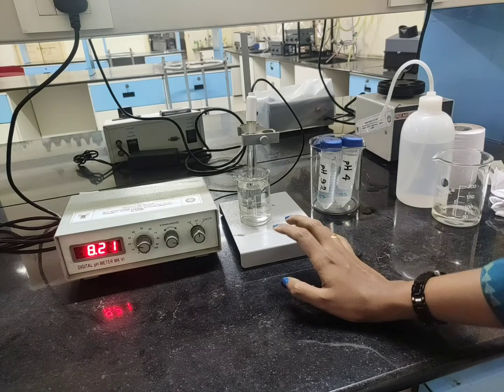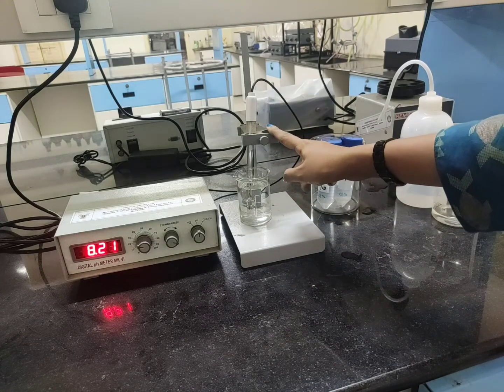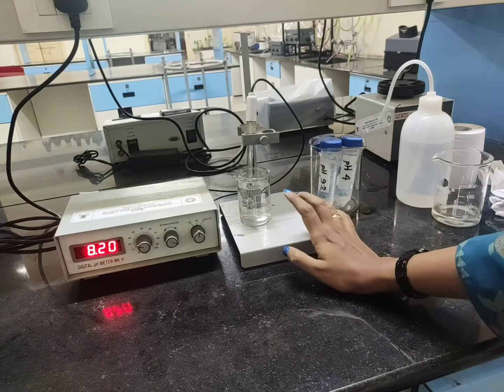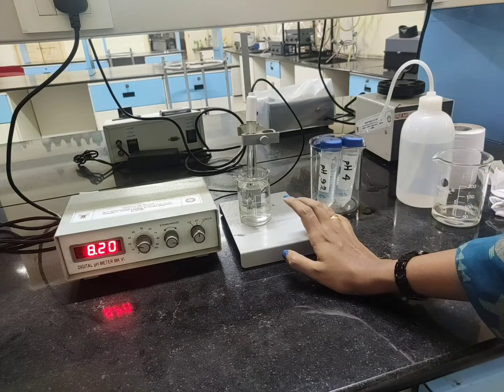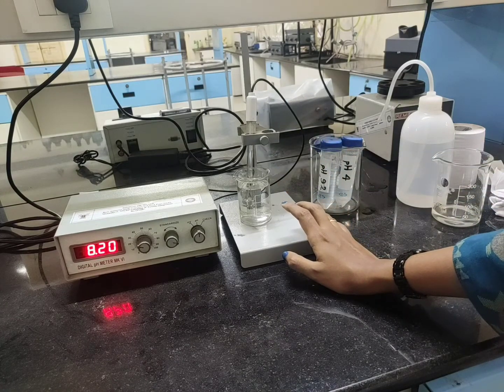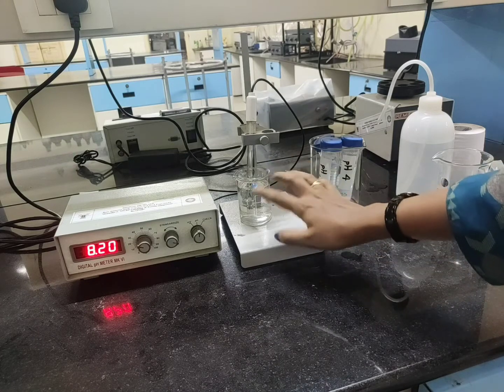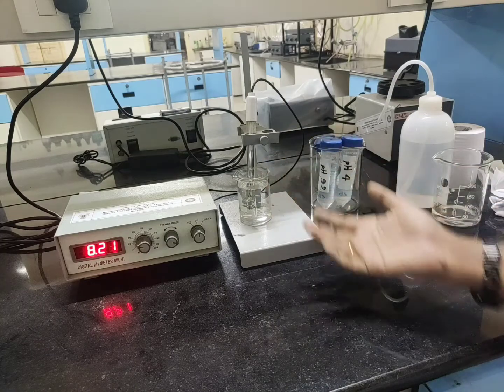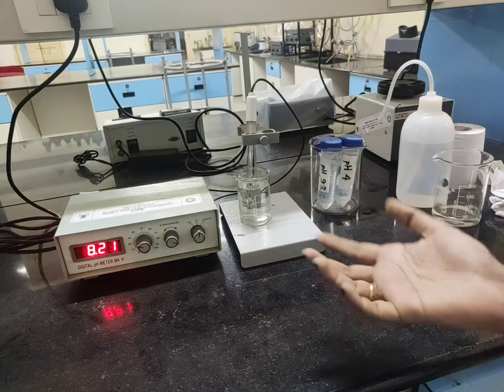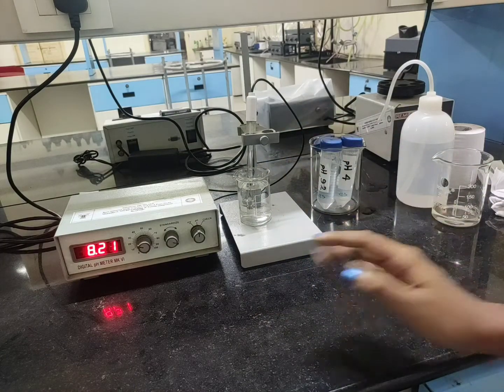Always make sure that you are dipping the electrode or the probe in KCl solution or HCl solution or even other water, but not distilled water. In case you put it in distilled water, the electrolyte that is present inside will get diluted. So later you won't get the exact value, and the sensitivity will not be there.